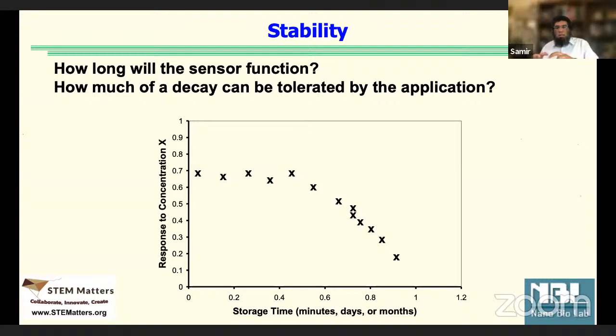So the electronics can sometimes cater for that change and use a new profile, the profile that they would have tested in a lab environment before they send out the sensor to sell. So that can alleviate this problem to some extent. But it is a very important aspect to know how stable it is and for how long.